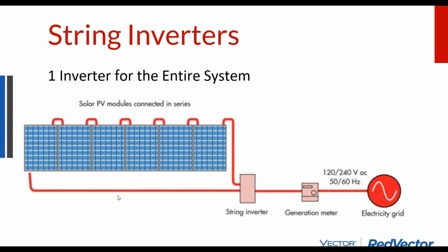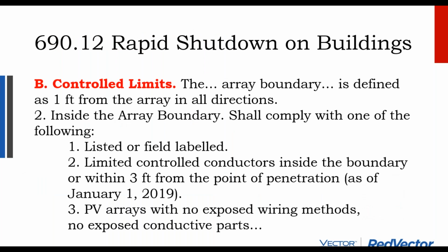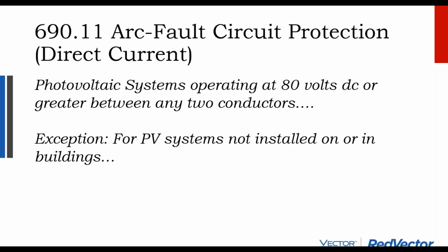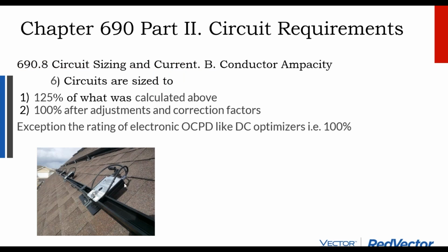And so there's this home run conductor between the inverter on the side of the building and the solar array that if there's a fault in that conductor, the inverter could be turned off, but the solar panels are turned on. And so you still have that high voltage conductor that needs to be turned off. And it doesn't matter whether that conductor is outside the array perimeter or inside the array perimeter, the high voltage aspect of the system needs to be disabled in the event of a fire. And so the way that we do that is we rely on these little boxes to go behind each solar panel, or in some cases, every other solar panel, not all cases, but in some cases, every other solar panel, so that these boxes contain the disconnects to turn the modules off on command.